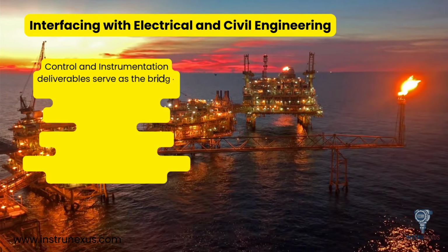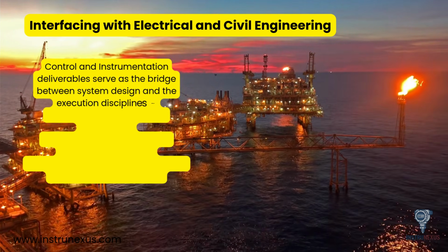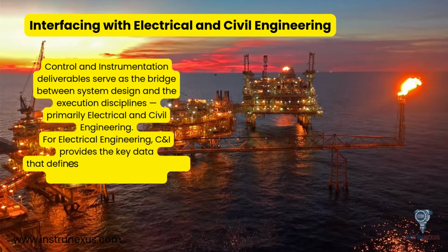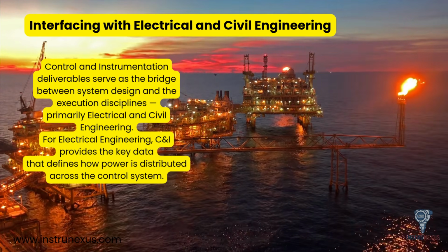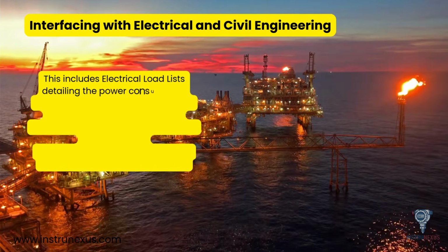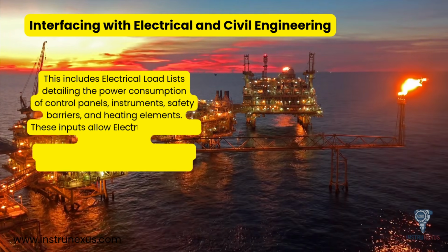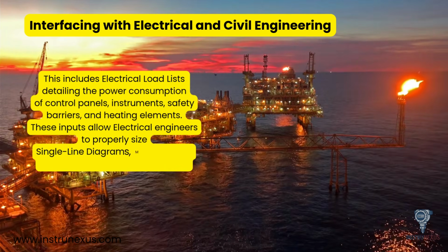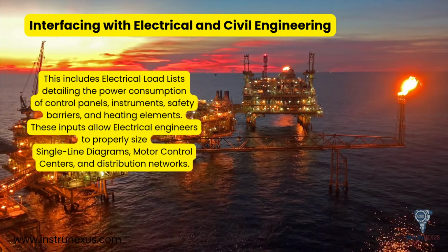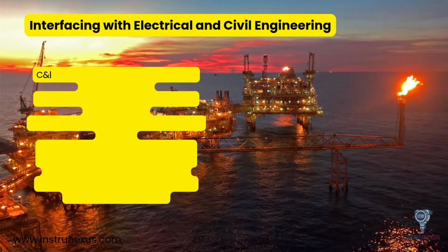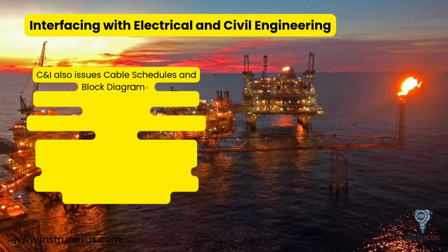buildable design. Control and instrumentation deliverables serve as the bridge between system design and the execution disciplines, primarily electrical and civil engineering. For electrical engineering, C&I provides the key data that defines how power is distributed across the control system. This includes electrical load lists, detailing the power consumption of control panels, instruments, safety barriers, and heating elements. These inputs allow electrical engineers to properly size single-line diagrams, motor control centers, and distribution networks.